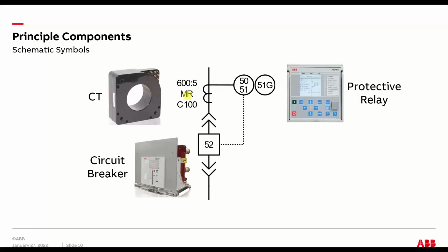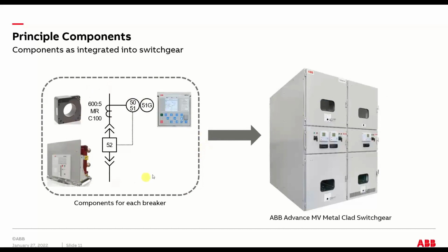And the 5 goes back again to the fact that they were electromechanical relays, which drew physical load off the CT. So standardizing on 5 amp gave them a little more power capacity, so they could drive the actual elements that make up the relay. That's just a little background. And this last number is an accuracy class for the CT. And then here's your circuit breaker. Same stuff. This is all pretty much medium voltage gear. And then here are the components that make up one breaker, and then they all go into, in some cases, a bigger assembly.